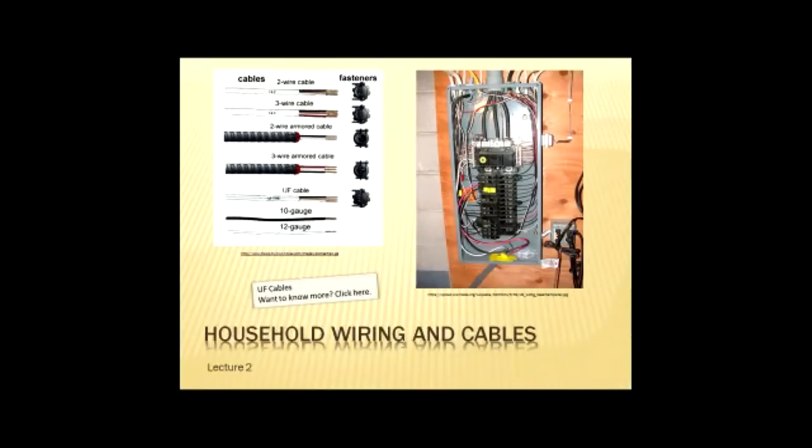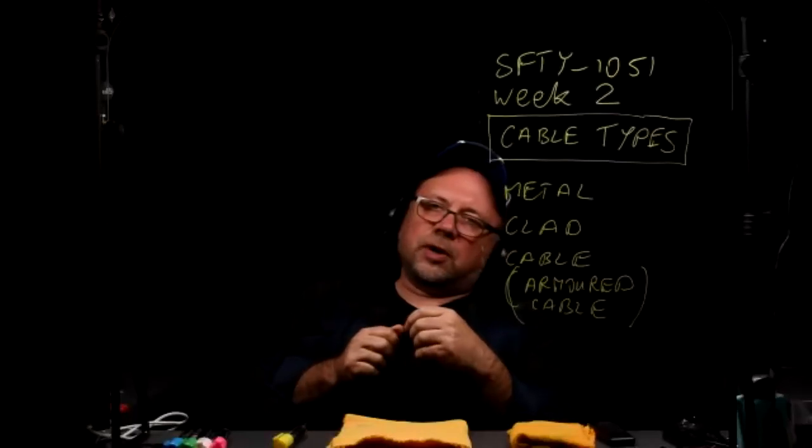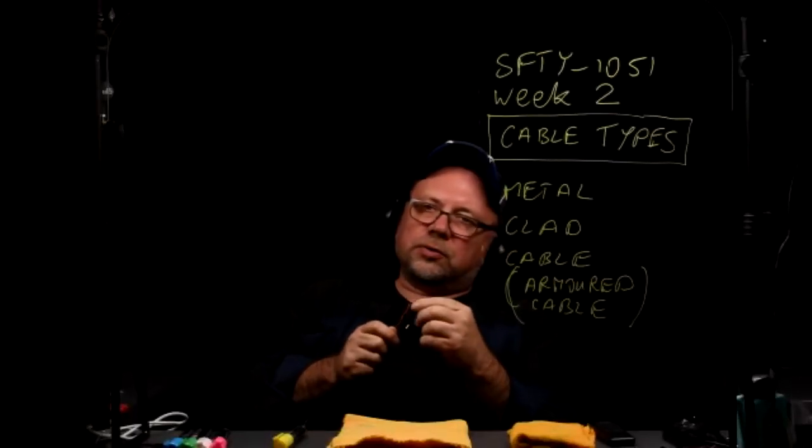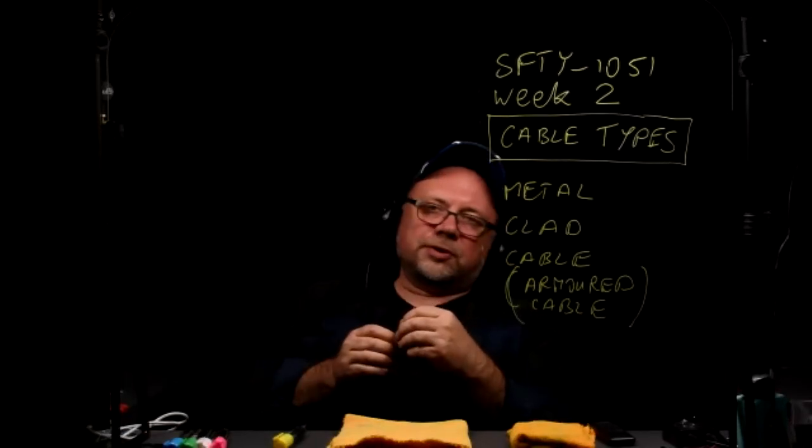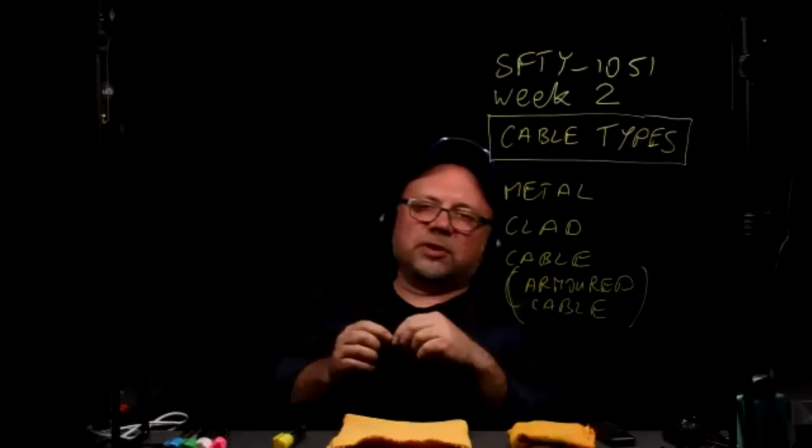You see two wire cable, but you can see three wires in there. Yeah, but it's called a two wire. There's another thing you're going to be able to see once you download this document. You're going to see that it says 14-2. That means it has two current carrying conductors and one ground wire, or you can just call that wire a bonding wire. And we're going to stop at some point. Why don't we stop right here, and we're going to find out what the difference is between grounding and bonding. Okay. All right. Grounding and bonding. What is the difference?